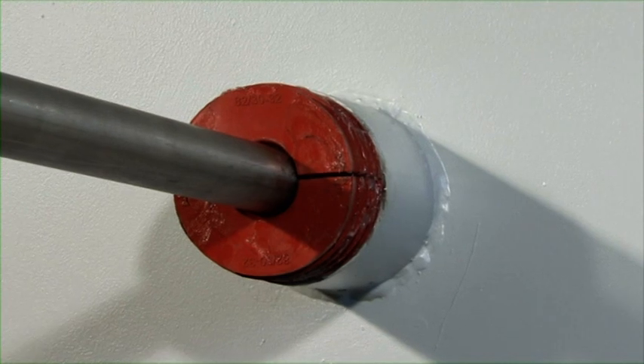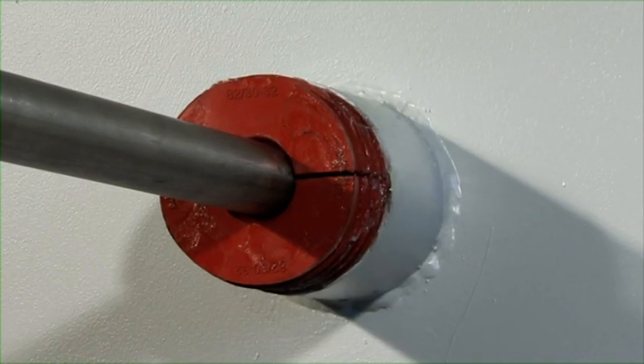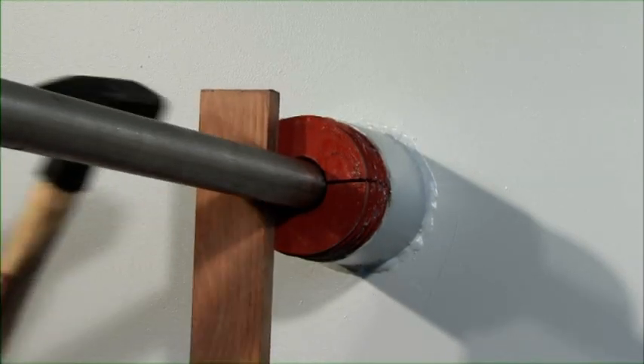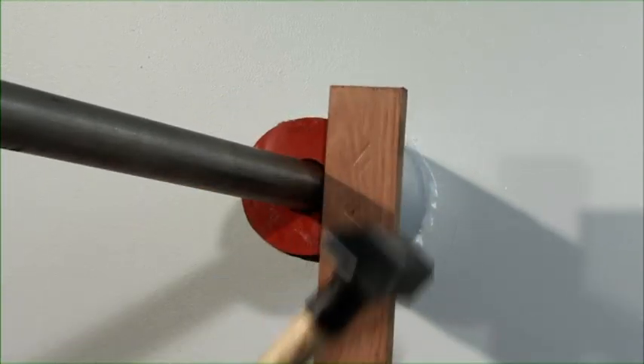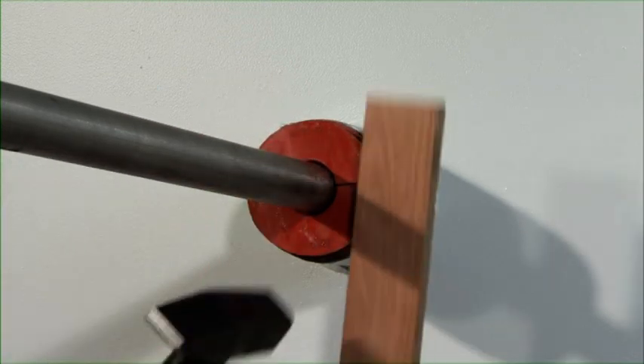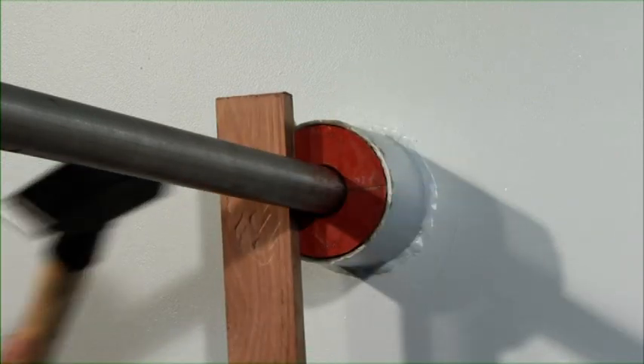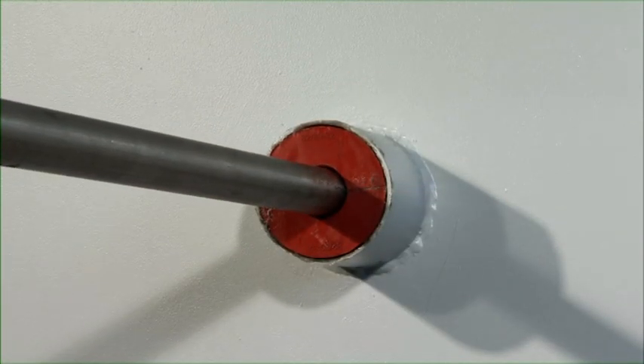The first serration is smaller than the other serrations to allow the conduit. Both halves are then pushed evenly, serration after serration, further into the conduit. This can be done by hand or by using a hammer and a piece of wood. Don't hammer directly on the plug to avoid damage to the sealing plug.